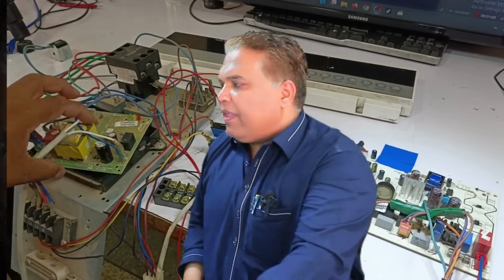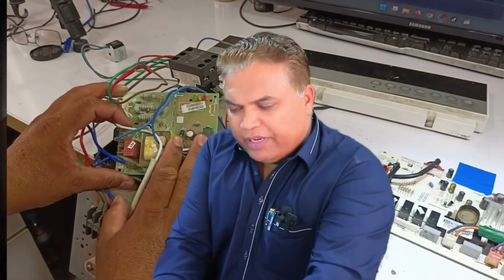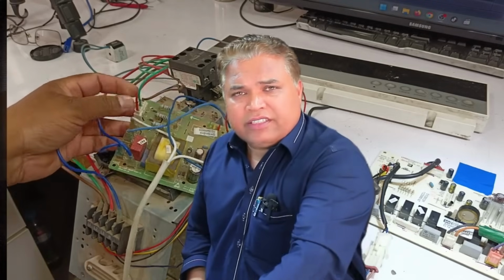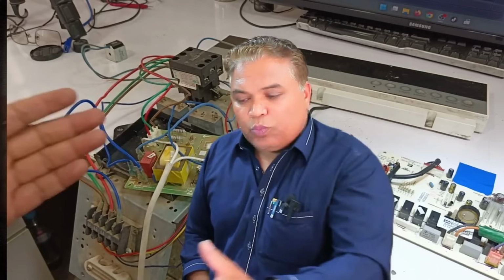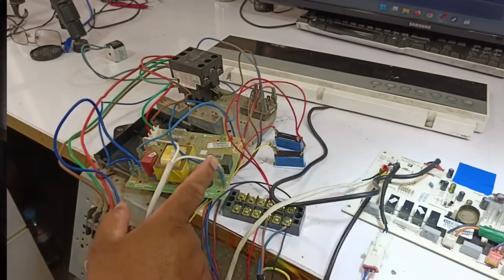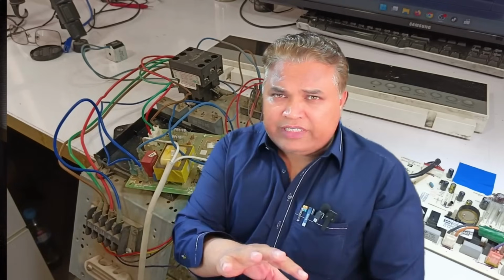The first fault is that if, for any reason, the outdoor PCB is not functioning at all, the indoor unit will still display the F1 error because the required signal will not be generated. The second fault occurs if there is a phase detection problem, meaning if any one of the phases is missing, then the circuit will again trigger the F1 error because the rest of the system functions will not operate, and as a result, the F1 code will appear.